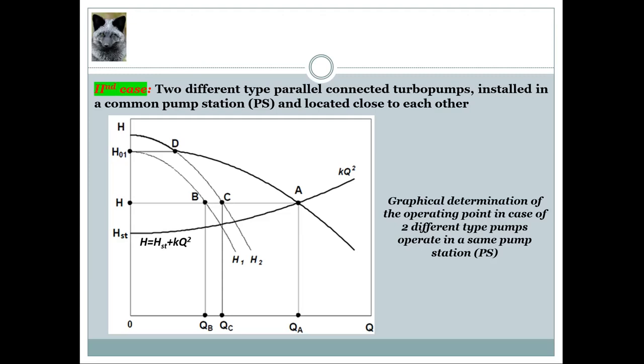The intersect points of the individual head curves of the two pumps with the pipe system resistance curve provide information about their operating modes when each pump operates separately. The starting point of the summary head curve is point D, determined by the zero flow rate of the lower head pump curve. At a head higher than H01, only pump 2 will ensure flow rate — this is important to remember.